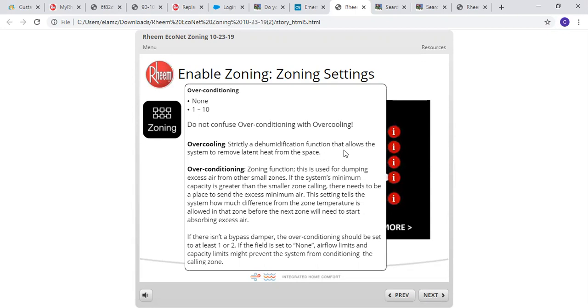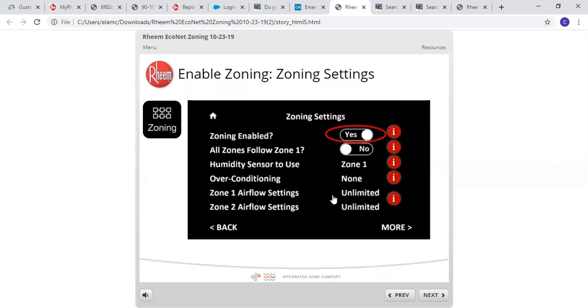If the system's minimum capacity is greater than the smaller zone calling, there needs to be a place where it can send that excess minimum air. This setting tells the system how much difference from the zone temperature is allowed before the next zone will need to start absorbing the excess air. So if you've got multiple zones, you can start dumping a little bit of air in each zone to prevent static pressure issues and faults. If you have a bypass damper in there, then that kind of takes that out of the equation. If there isn't a bypass damper, the overconditioning should be set at least 1 or 2. If the field is set to none, airflow limits and capacity limits might prevent the system from conditioning the calling zone. So they're recommending you at least put 1 or 2 under the overconditioning option.